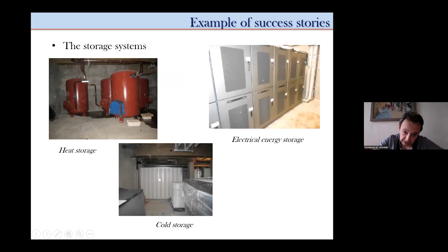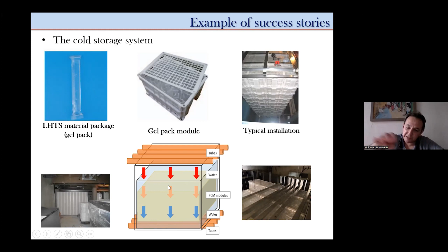What we have used is a kind of gel stick which melts at 7 degrees, and we put them in a kind of bucket, using several buckets like this. The idea is to bring in water, because we are using water for the absorption chiller, and the water melts the phase change material, and here we retrieve the cold water. So the idea is to use a large medium of phase change material, as you can see in the image, to keep it approximately stable at 7 degrees.